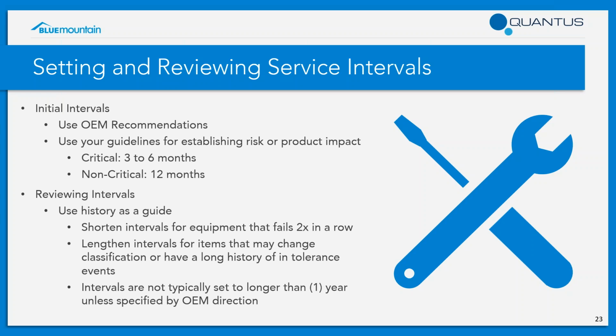And if it successfully passes calibration, you can evaluate it for restoring the device to the original interval. And typically, that's what we see, and that's how people handle it. It's going to be up to you guys and the historical performance of the device. And Ryan, you brought up a valid point earlier, from a historical standpoint, right?